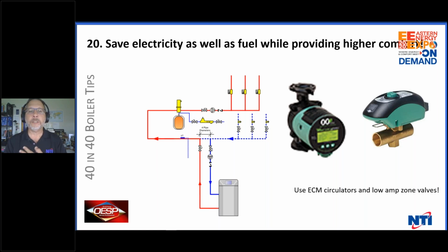Please, variable speed circulators save energy, and low amp draw zone valves like the new Taco valves are phenomenal. The original Taco valves drew almost 5 times as much energy and drew it all the time as compared to the new ones. Honeywell's zone valves, the V8043F draws almost twice what these do. Plus, they're powered all the time, whereas this zone valve is powered open and then powered closed.